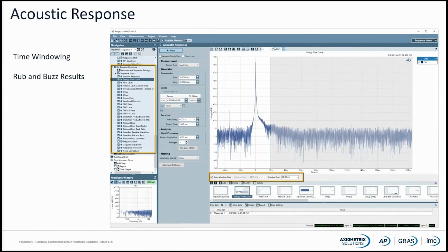The APX 500 acoustic response measurement is a chirp-based measurement with time windowing to gate or window out acoustic reflections from your results. If you don't have an anechoic chamber for making electroacoustic measurements, this feature will help. Acoustic response measurements can be made in closed loop or in open loop configurations.